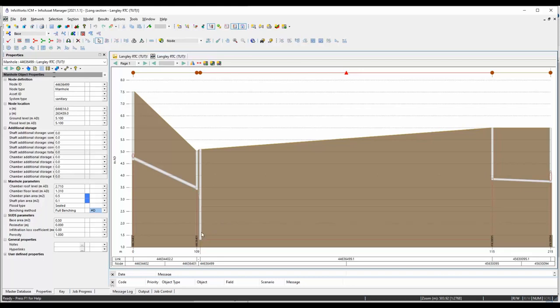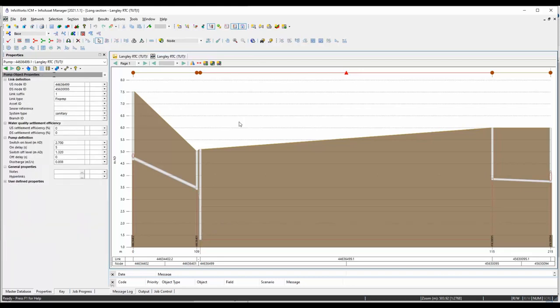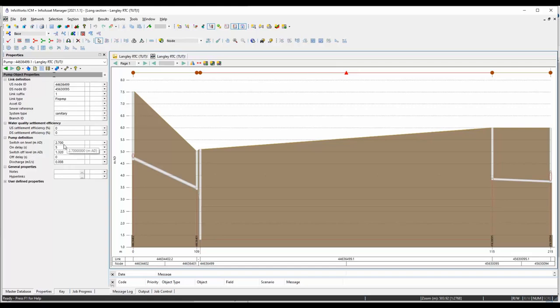We want to use a real-time control rule to define when the pump should be turned on and off. If you double-click on this, you can see this is a fixed pump. The pump will be turned on when the level is 2.7 meters above the datum of the wet well, and it will be turned off at 1.3 meters. You can see those two lines - 1.3 and 2.7 - these are the absolute level values. What we're going to do is override this and write a new rule.